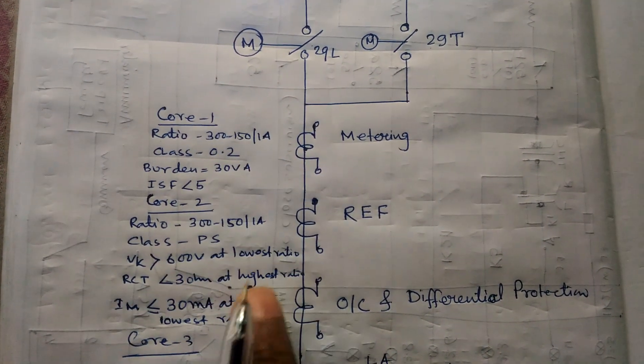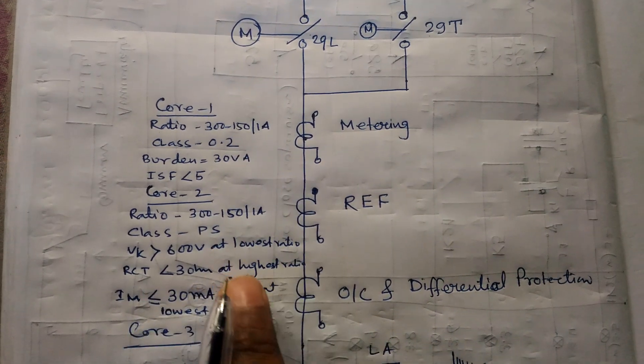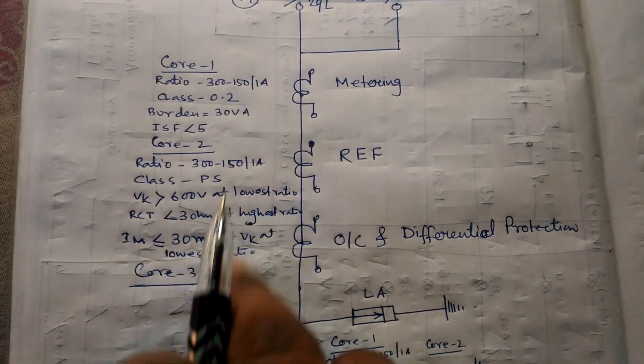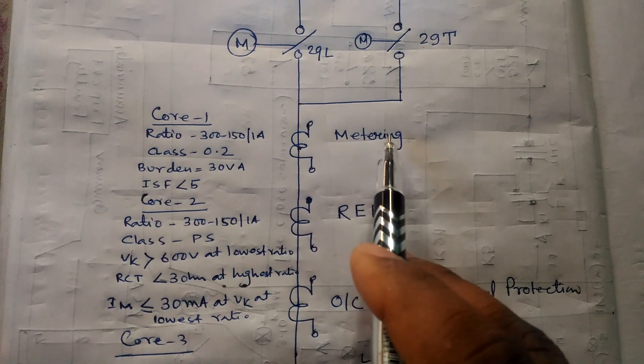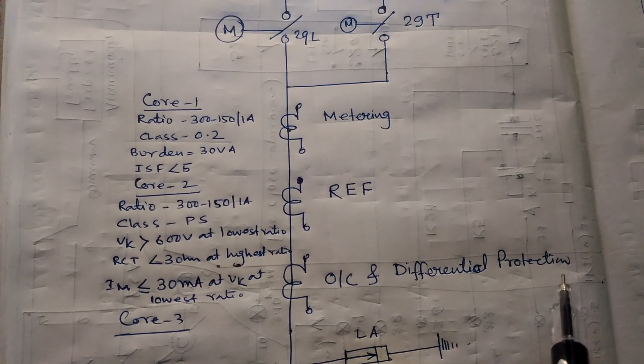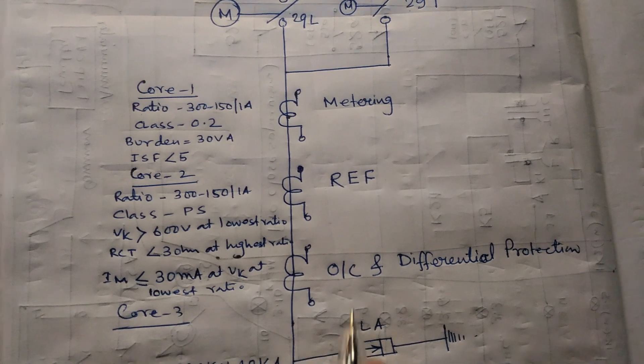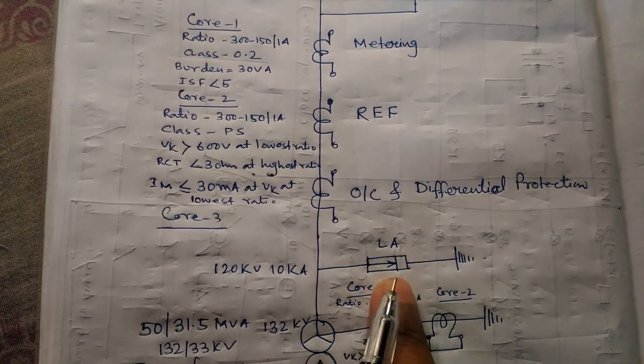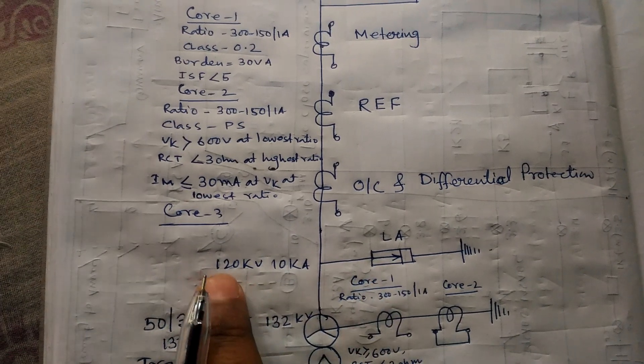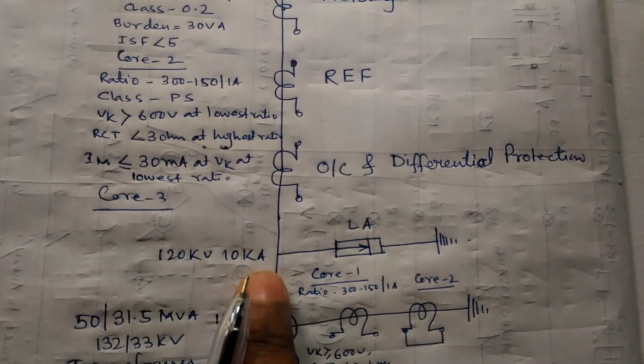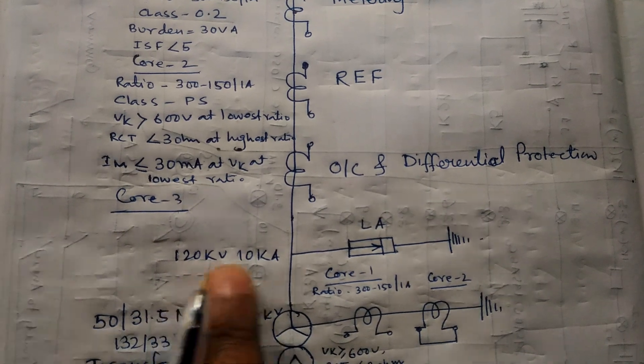We use a CT of three cores, 300/150/1 ampere, Class 0.2, burden 30 VA, 2PS cores. The first core is for metering, the second is for REF protection, and the third is for overcurrent and differential protection. Lightning arrestors are used on the 132 kV line side.